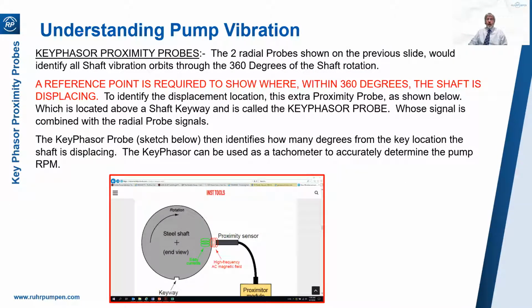Now, as well as the X, Y, Z proximeters, you'll also have a keyphasor proximeter aimed at a keyway. This will identify where the shaft displacement that is measured by the X and Y probes is occurring, referenced to this keyway. So for example, it identifies that a shaft might be bent at 20 degrees away in a clockwise direction from the keyway, for example. It also can act as a tachometer to accurately read the speed.